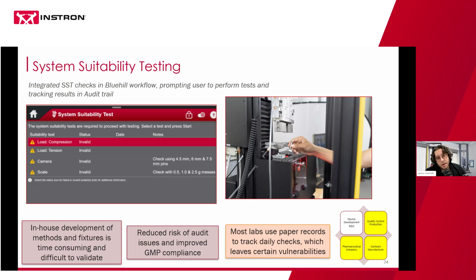We wanted to completely streamline that process, digitize it, bring it into the Bluehill software, so it leaves no room for error or misuse of the system by an operator. So having system suitability built into the software will essentially prevent them from running tests until it walks them through the process to evaluate the performance of the load cell, the camera, and the scale.